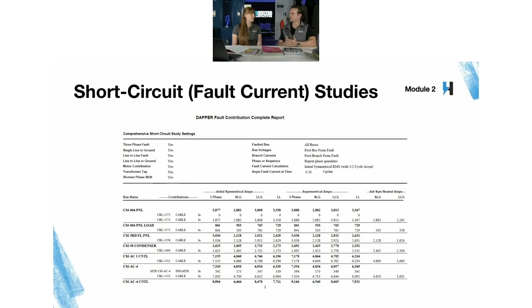Yeah, let's avoid that. All right, so here's a result of what a short circuit or fault current study might include. And this one is provided by using the SKM Power Tools software. Yep. So basically, you want to talk about how to interpret this data, or kind of quickly run through some of the information? Sure. So in engineering terms, there's several different fault current studies you could do. You've got single phase, phase to phase, 3-phase, bolted fault current, short circuit studies that are done. And all of this information for the system is put into a report, nice and neat, like you see on the screen here. So you can reference it anytime.